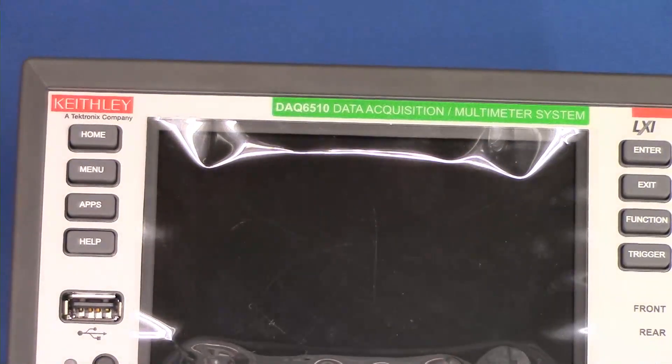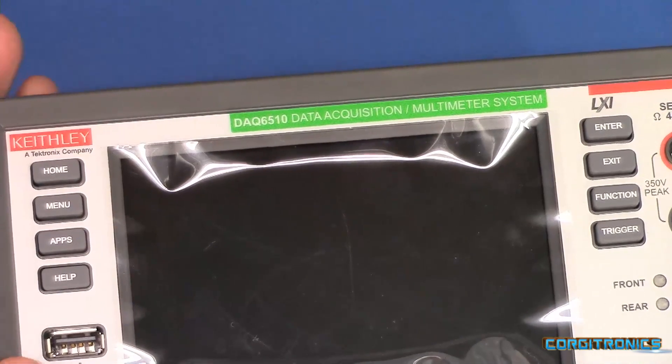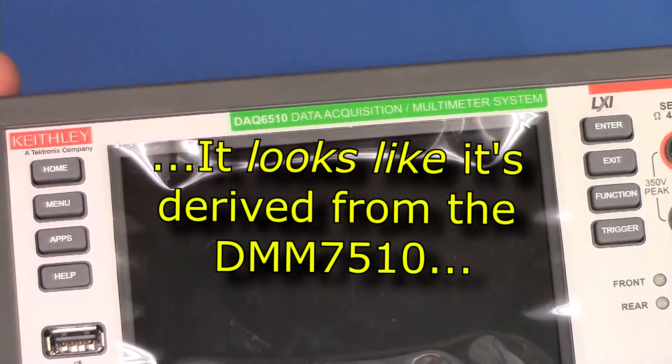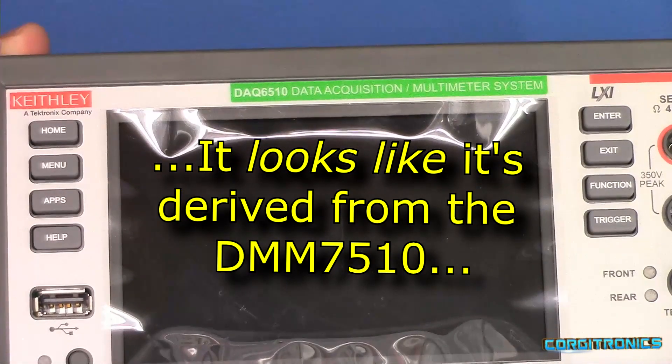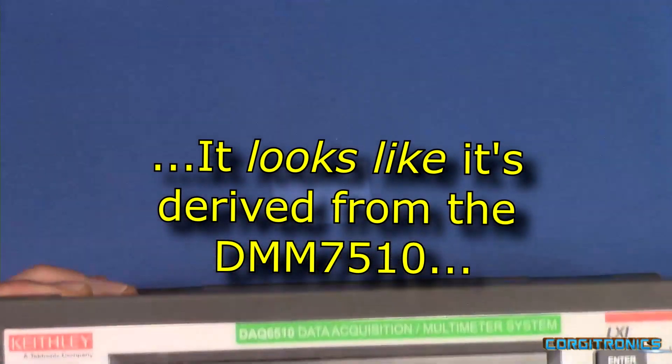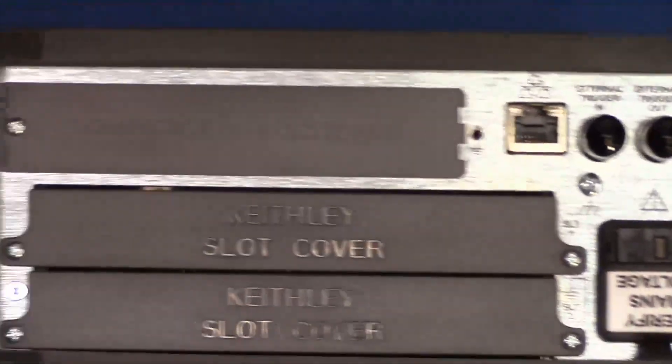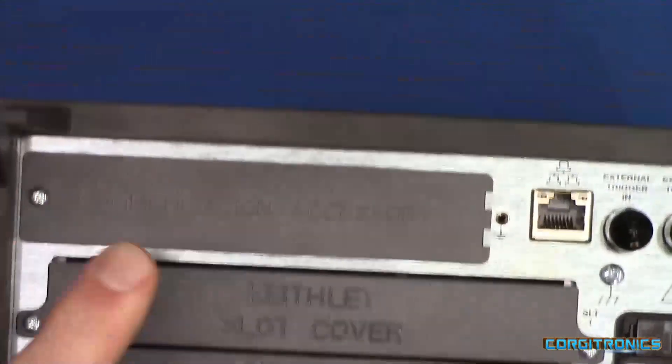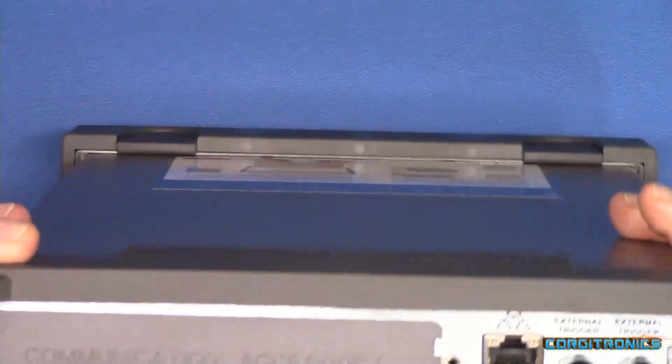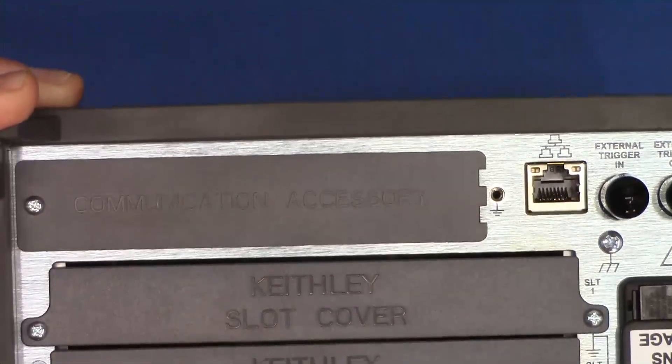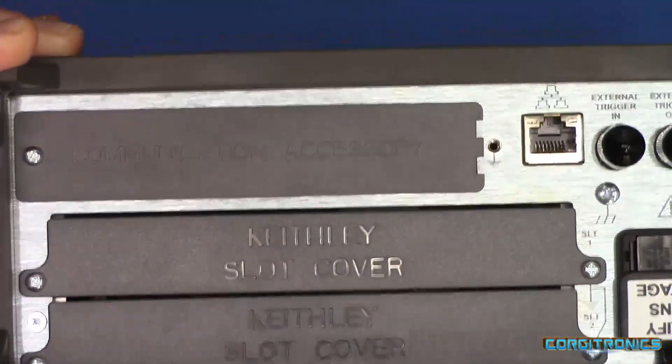It is a DAQ 6510. This is a six and a half digit meter based upon their DMM 6500 series, which itself is derived from the DMM 7510, which I have on the bench. Except that this also has slots, options for additional channels. This is a scanner card. This takes scanner cards in, and you can have up to 80 channels with this.